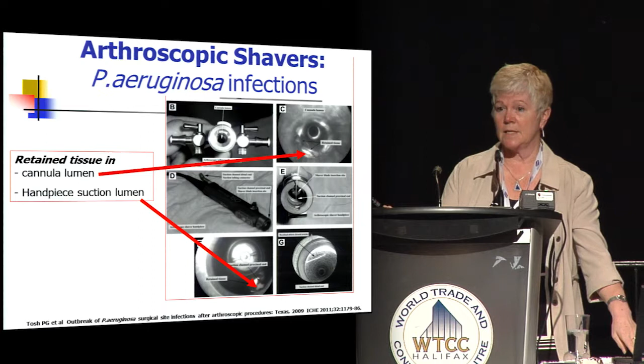But it was interesting to me because based on this incident, the FDA actually issued an alert. I don't know if you're aware of it or not, but there was an alert that came out in conjunction with this that said to endoscopy clinics, you should be inspecting the inside of your arthroscopic shaver handpieces using fiber optic small narrow devices that allowed them to see the inside. And I would bet my bottom dollar that out of all the people in this facility, not one of your facilities has probably actually implemented using fiber optics into the handpieces. I know at our facility that isn't something that is being done. But it's the concern of the FDA that it's really the retained tissue that is the basis for that biofilm buildup and the inability of steam sterilization to actually kill organisms that are inside the tissue. So the key conclusions were that there was inadequate cleaning. Tissue remained in the lumen of the handpiece despite cleaning and steam sterilization, and they were following the manufacturer's instructions for the handpiece.